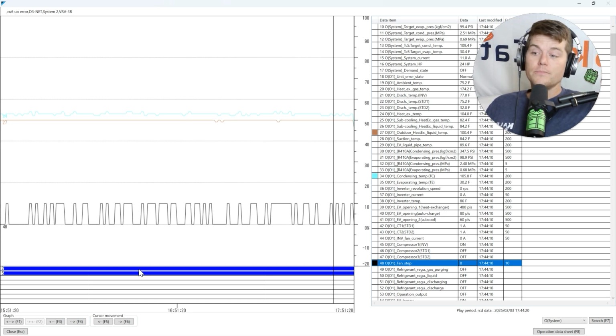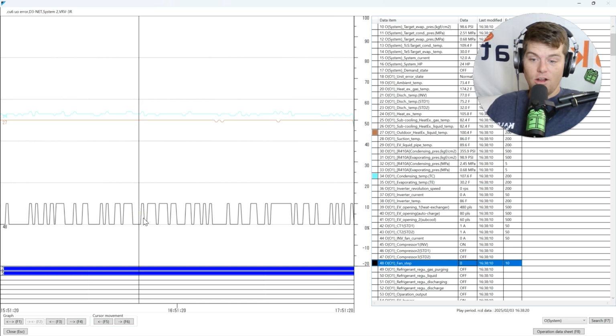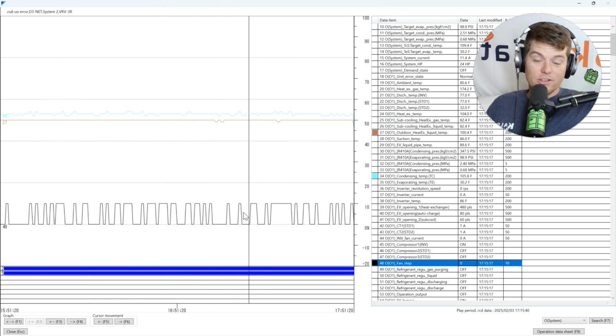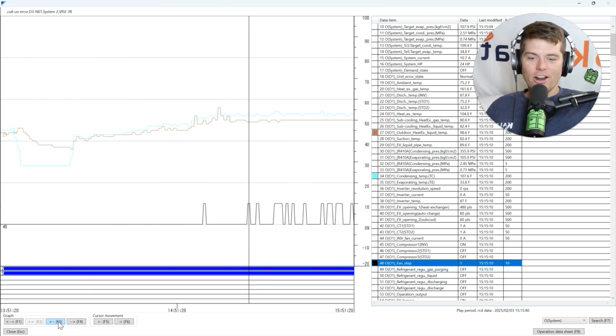Everything's in full cooling. And I could walk past a condenser where the fan would be off on one module and turning on and off. And this is what we see here. Off, on, off, on, off, on. This looks like square waves on an oscilloscope for VRV comms. This is fan steps. 0 is off, 1 is on. And then the other module, the fan never runs, because again, no refrigerant's flowing through it, so why would it run? This is a dead giveaway on an undercharge scenario.